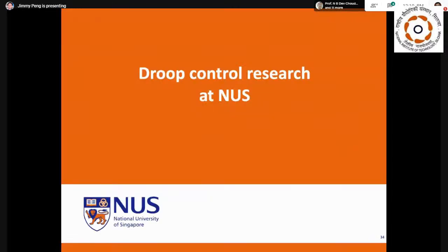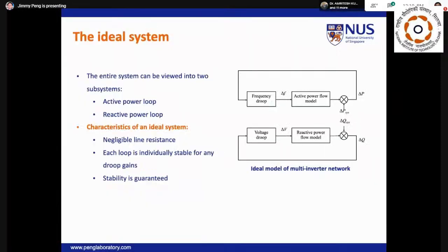So with that background covered and the problem outlined, I will now proceed to present one of our Droop control designs recently developed within our group. The control of a microgrid consisting of multiple inverters can be divided into 2 subsystems. The active power loop manages the active power sharing among the inverters, whereas the reactive power loop regulates the voltage of the microgrid. The stability factors that influence both loops are Droop coefficients and the line and load impedances.